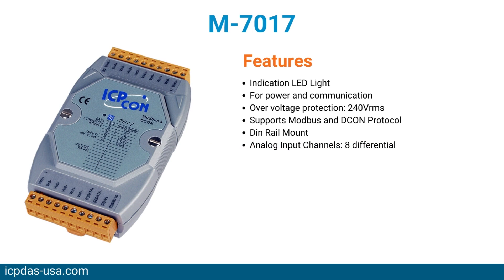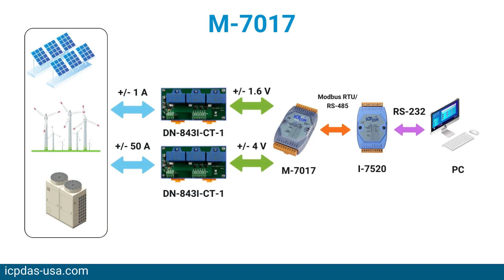The M7017 is an 8-channel voltage and current input module. The M7000 series is a family of network data acquisition and control modules that support Modbus RTU. They can be remotely controlled using a set of commands called DCON protocol. With the Modbus RTU protocol, it can easily communicate with the most popular SCADA and HMI software and PLCs.